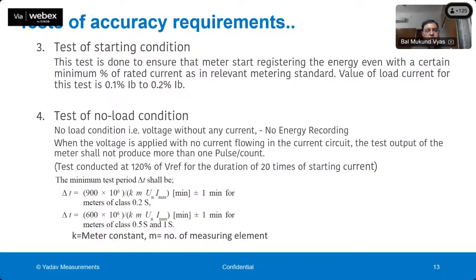So there is a specified minimum starting current in the standard, and the typical value is 0.1% of IB. IB is the basic current. That amount of current is passed to the meter, and it is checked whether the meter has started recording the energy in the register or not. So this is the test of starting condition.